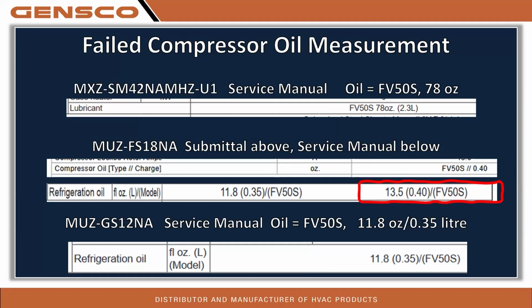FS18, and it can be conflicting information. The upper line came from the submittal. It says ounces and then says 0.40. My question would be, is that 0.4 ounces or 40 ounces? And they put a decimal in there. That 40, as you see from the service manual in the line below that, is actually 0.4 liters, which is 13.5 ounces. And then the GS12 at the bottom from the service manual again, 11.8 ounces or 0.35 liters.